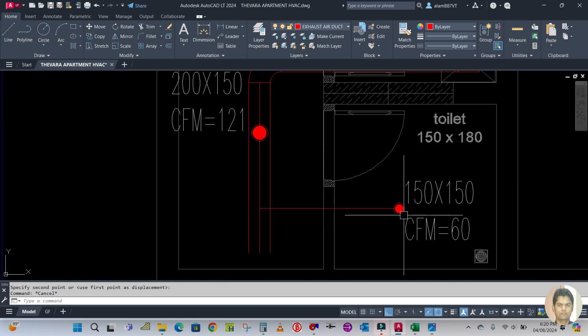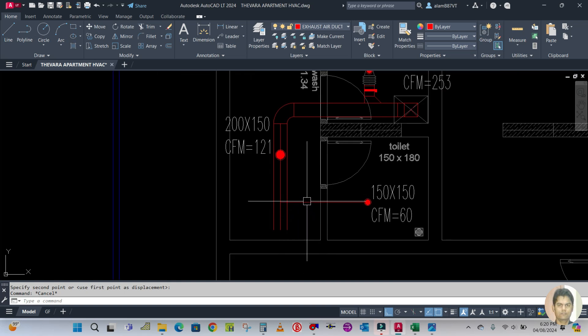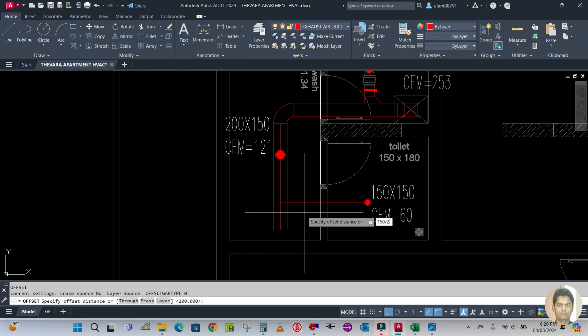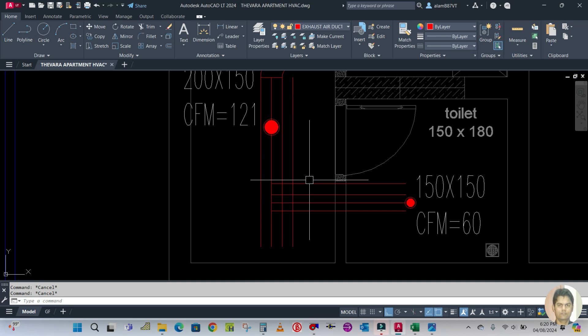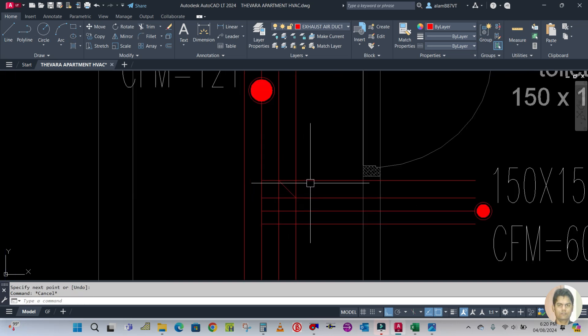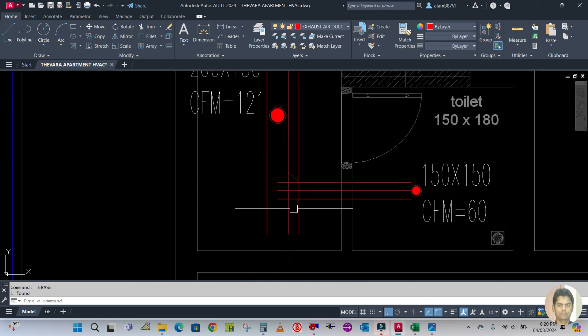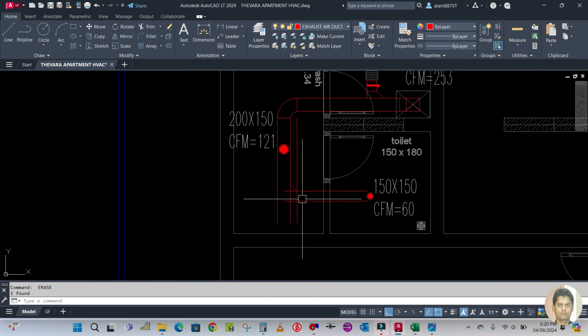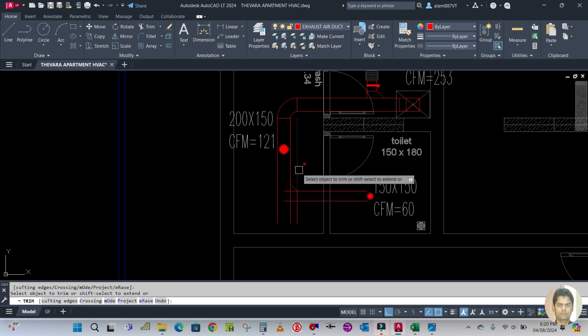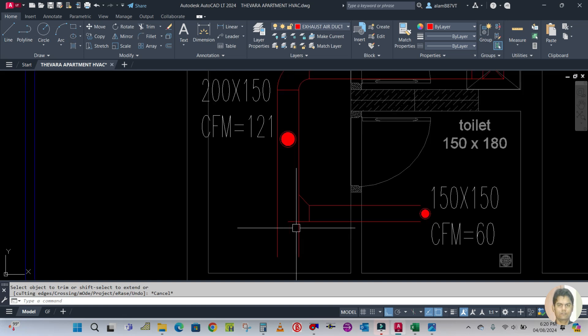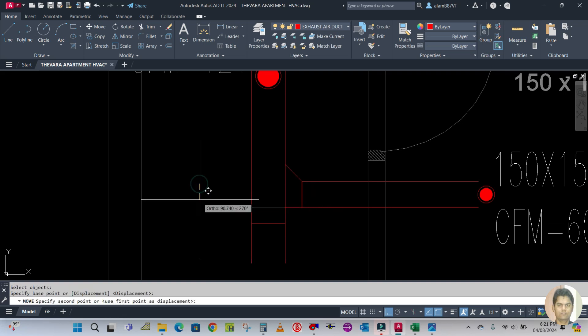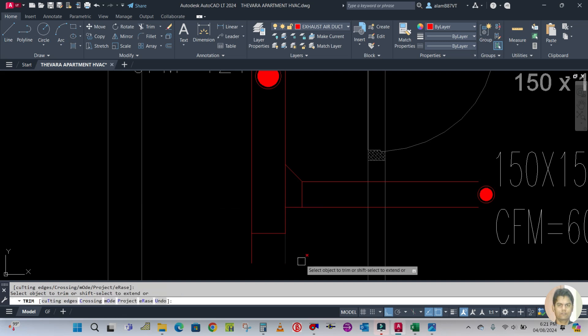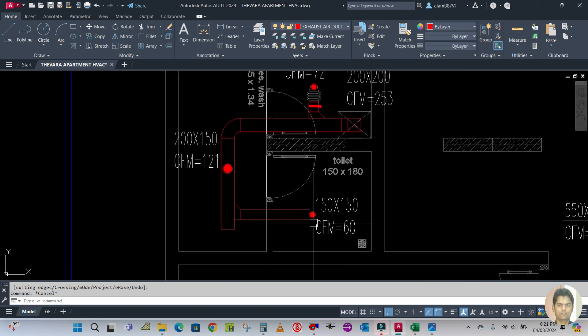The duct size here is 150 by 150. Create the branch duct first — 150 divided by 2, offset this side and that side. The shoe neck is 100 mm, so offset 100 mm. Create the shoe neck from this point to this point, erase the line, and erase the center line. Trim the extra line, draw an end cap line, move 150 mm, and trim the extra line. This is your shoe neck.